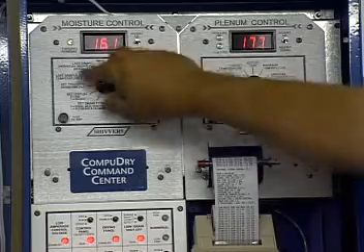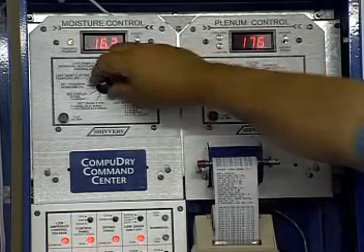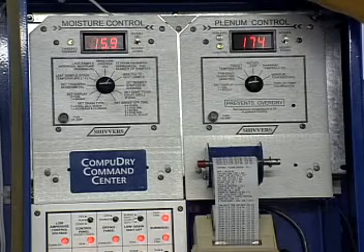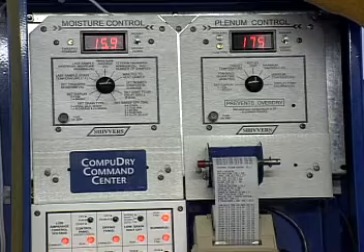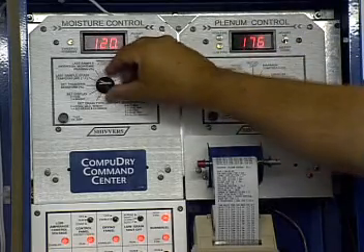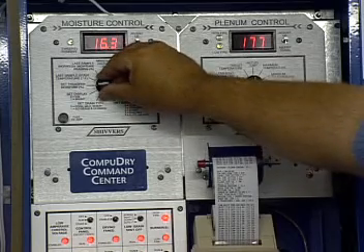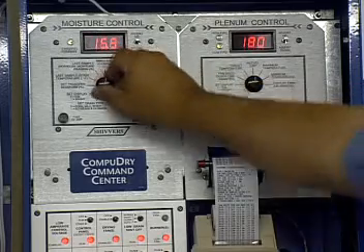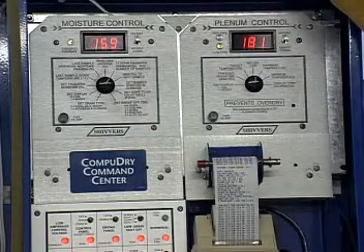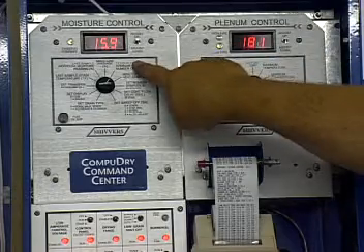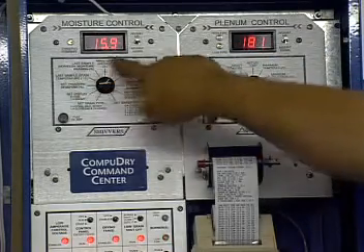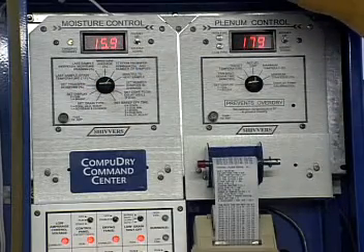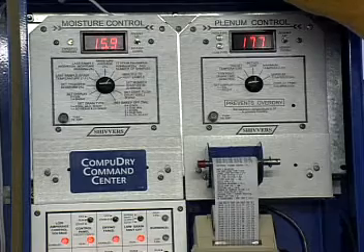So what you want to do is raise this to 16.3, which eventually is going to give you 16.1 up there. That's going to give you 16.1 over into the bin, because every time this takes the last sample, it's always 16.1 or less before. So all we're doing is raising this so we can get 16.1 up there. But do that after you've run it a day. Look at what it says up here, and what this says right here is what you want up here. So just change this by the difference. It's usually going to be 1 to 2/10 of a point. But that's going to pick up a little more capacity for you.